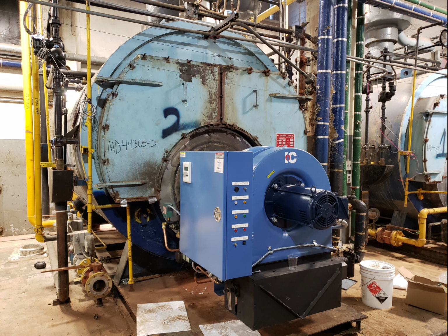So now any pressure that you have, how long do you think this thing will hold 2 psi for? First, you have to go through the post-purge once it reaches the cutout limit. That's going to be at least 30 seconds.